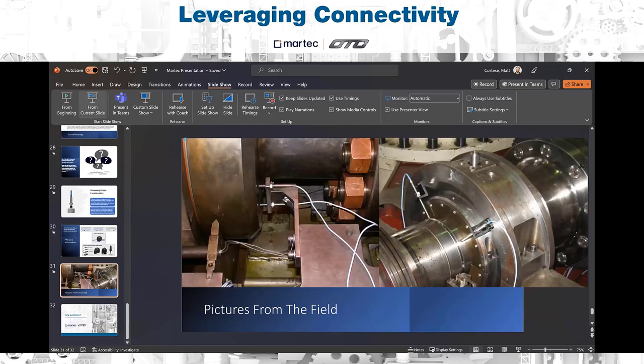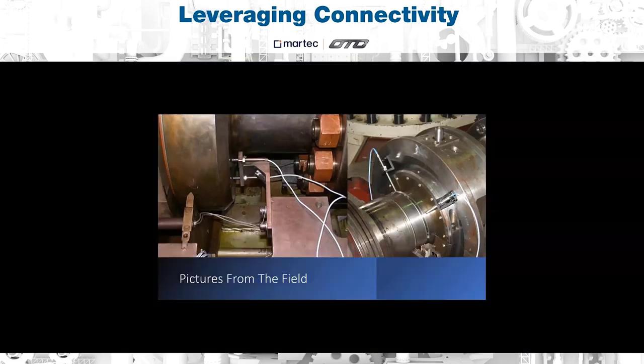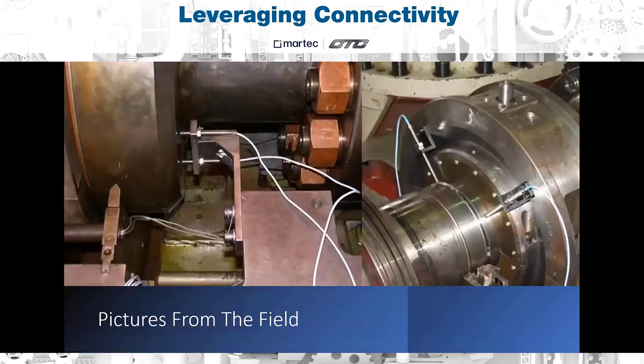But as you can see, that radial picture on the right there, if you have the right kind of DAQ system, for instance, like a Bentley Nevada 3500 rack system or something like that, you can take that data and actually perform orbital analysis, where you can track both the vibration and position of the shaft's centerline in that orbit, which is much similar to a vibration analysis with normal accelerometers. You can diagnose a whole field of different issues by examining the orbit of that shaft.